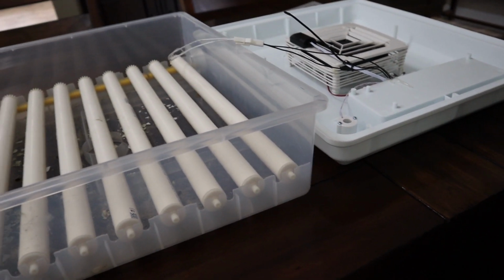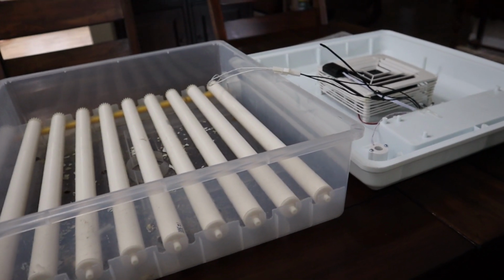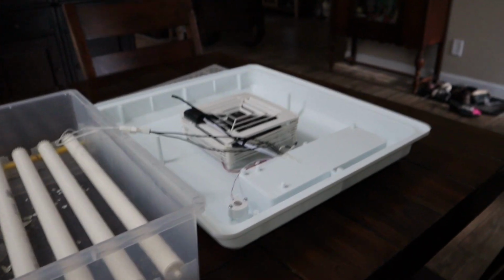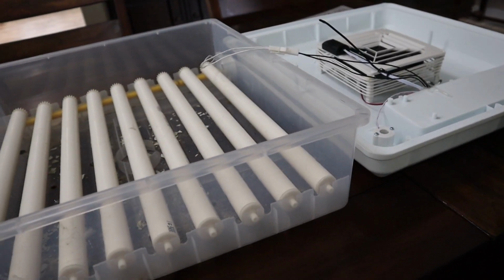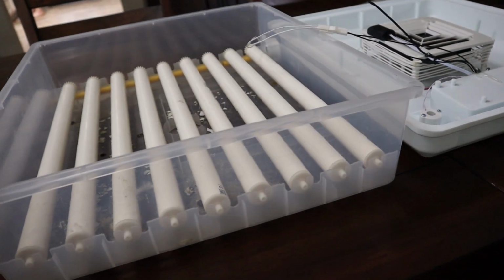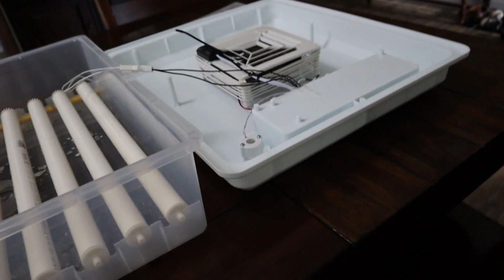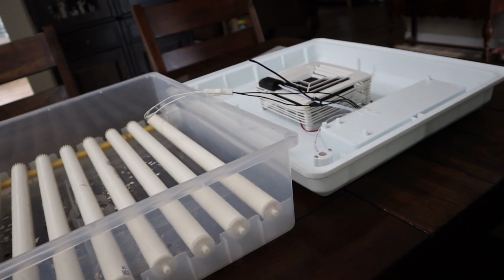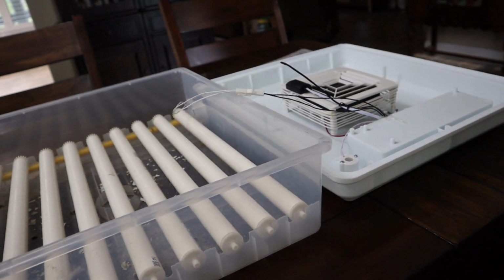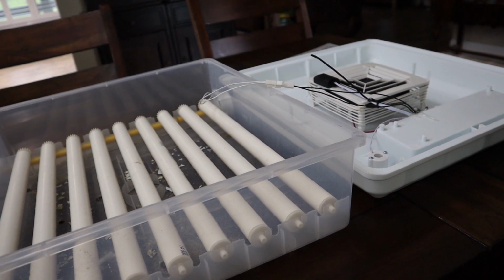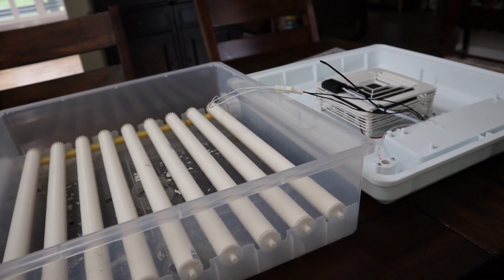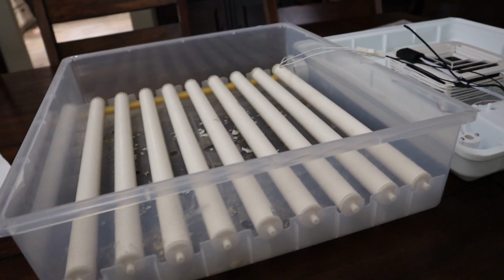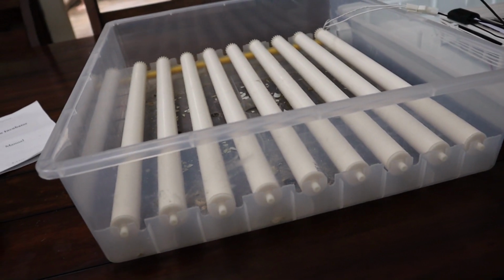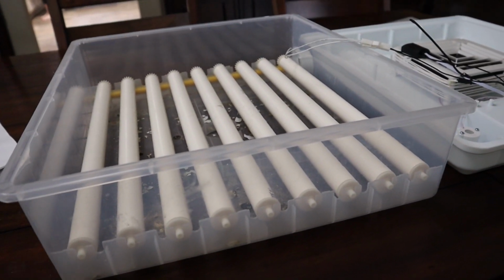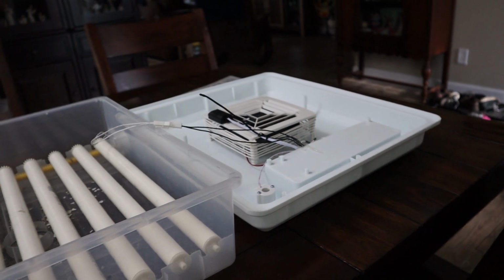38.9 degrees. So it maintained the temperature, but that heater had to work a lot harder, because I have to believe some of that hot air was able to escape since there is no seal on this unit. What you have on the Humidifier is all styrofoam, which keeps in not only the humidity but the temperature too—it's essentially a styrofoam cooler. That was a big issue, though I don't know if it was a big issue over the long term since that heater was able to keep up.